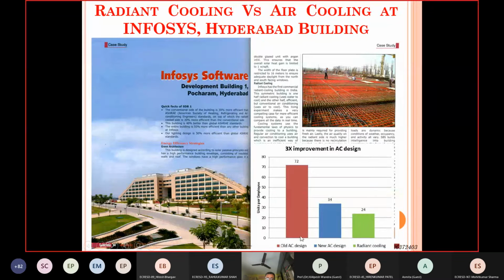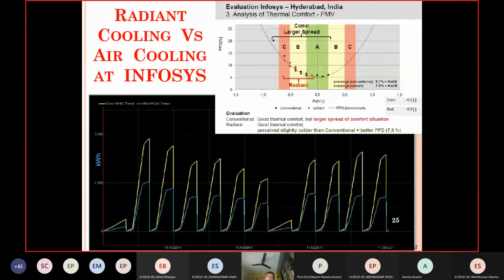And it is seen from this chart that the old AC design would consume much higher energy units per employee. While the new AC design, though conventional, is highly efficient, and it consumes almost half of this, right? And the radiant cooling consumes even less than that. Right, so it has been demonstrated that the radiant cooling system is much more energy efficient as compared to the other technologies. And also it was shown that it provides you better thermal comfort. That is seen with the help of this graph. And here the energy consumption by conventional and the radiant cooling is shown with time.